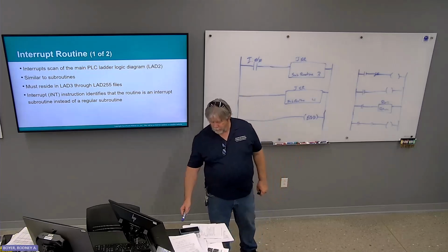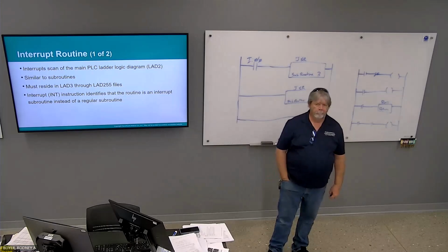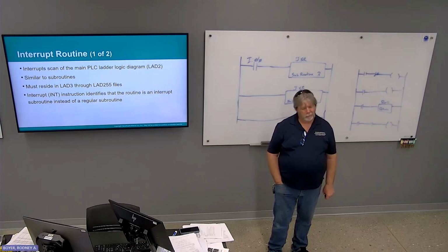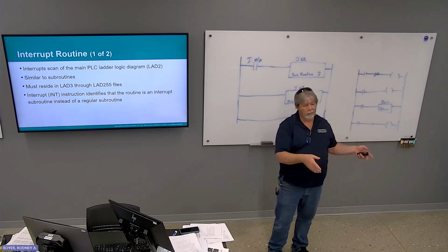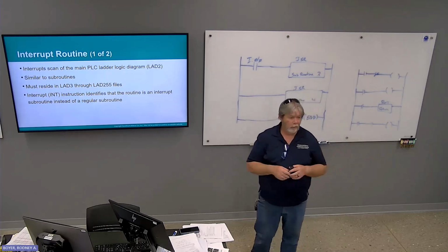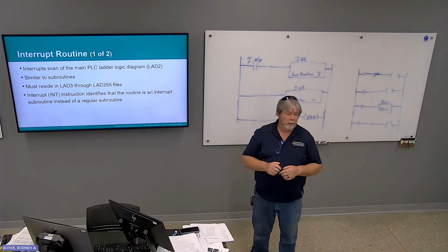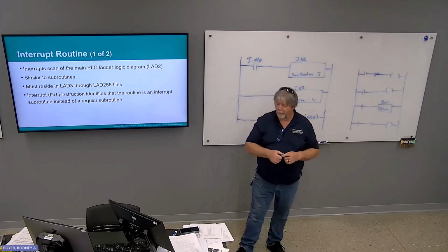Interrupt. Interrupt is an unconditional, no matter what you're doing, go process that subroutine. Which, if you have a separate fault routine, depending on what the fault is, you may need to, whatever it is, stop and go process the fault routine. You know, maybe you have a tank full of acid that's getting ready to run over and your high limit hits. I don't care what else you're doing, stop and go turn on the alarm bells and the whistles and the flashlights and, you know, all kinds of other things.